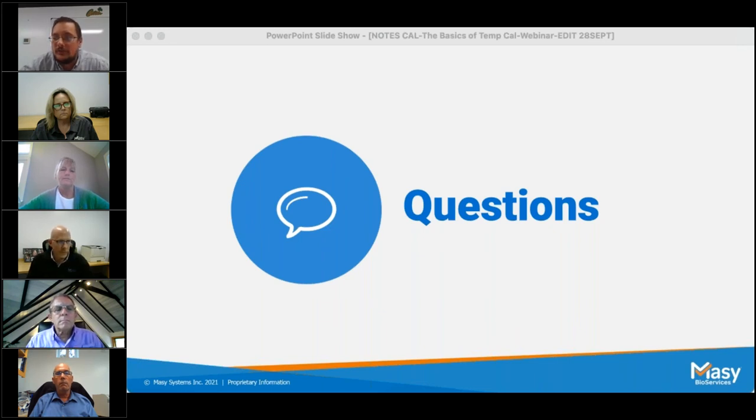The other thing it does for you, and we have another webinar on this, by the way, is that if you're right at the tolerance limit of whatever you're checking, there's a 50% probability that it could be falsely in or out of tolerance. So by nominalizing that, we help mitigate the effect from measurement uncertainty. If you want some more information on that, there's another webinar that we have, and we could send somebody the link if anybody's interested. Yes, definitely. We'll send everyone a follow-up email with links to our YouTube channel and our additional webinars.